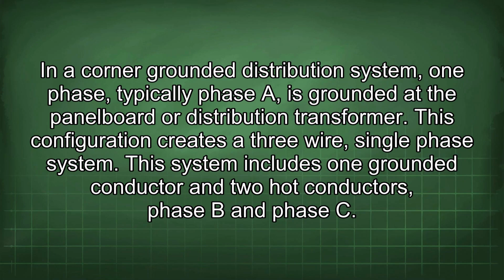In a corner-grounded distribution system, one phase, typically phase A, is grounded at the panel board or distribution transformer. This configuration creates a 3-wire, single-phase system. This system includes one grounded conductor and 2 hot conductors, phase B and phase C.